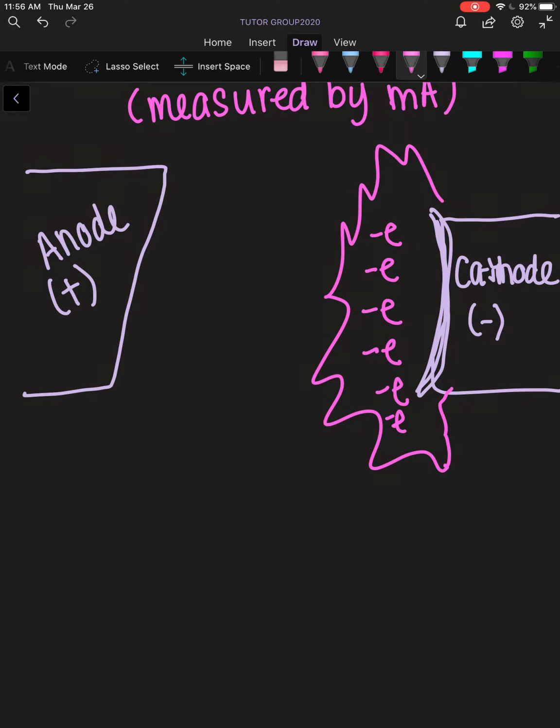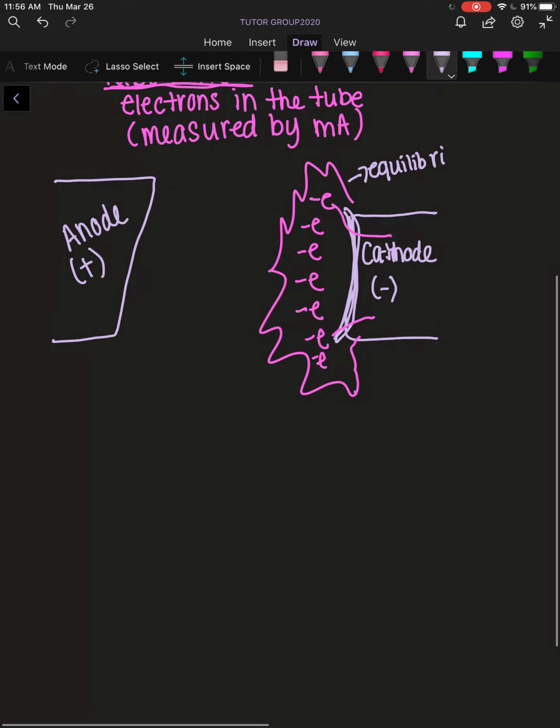And remember, you cannot have any more than the amount that you set at the control panel. If one comes in, then one will be going back in. Remember that in the tube, it has 3 wires, one for the electrons to come out and one for the electrons to go back into the tube. But we have to keep an equilibrium. Now, the other wire, remember that I said there were 3 wires right here. That is for our kVp.